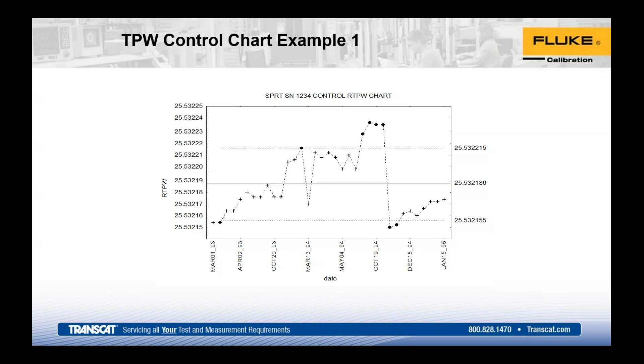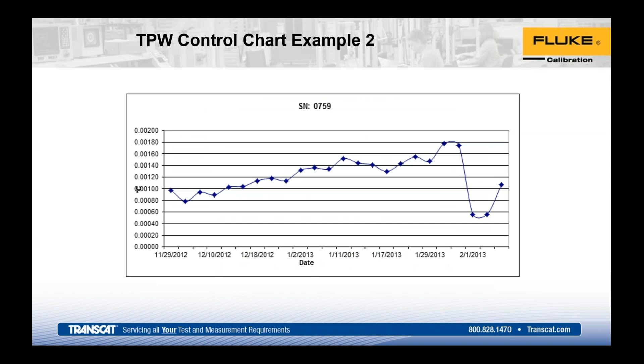So again, what you're going to do typically with your control chart, this one is done in temperature. This one was done in resistance. So with the resistance side here, basically you take the difference between the resistance reading you're getting and the reading from when you started, and if it's a 25 ohm probe, you divide by 0.1. If it's a 100 ohm probe, you divide by 0.4, and that gives you a rough approximation of shift in degrees C. Or again, you can just do it in temperature and watch your drift in temperature.